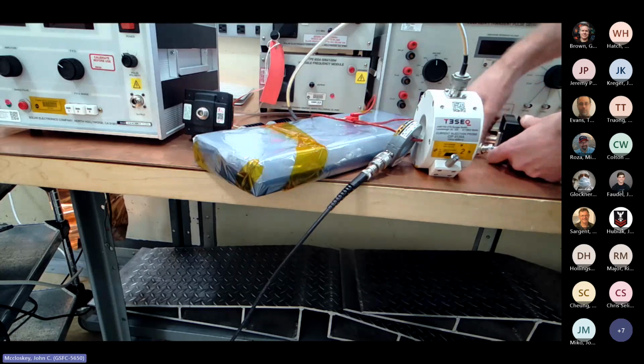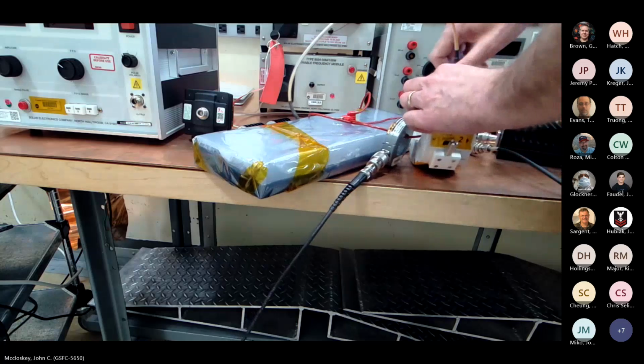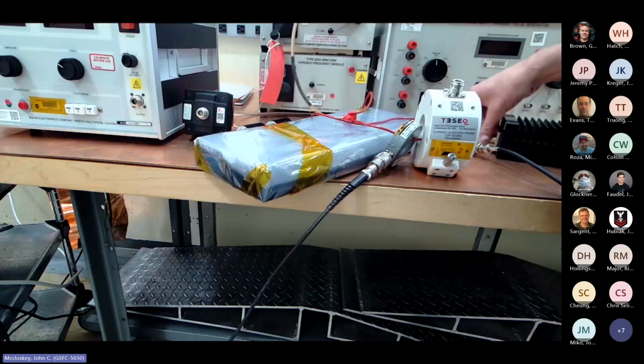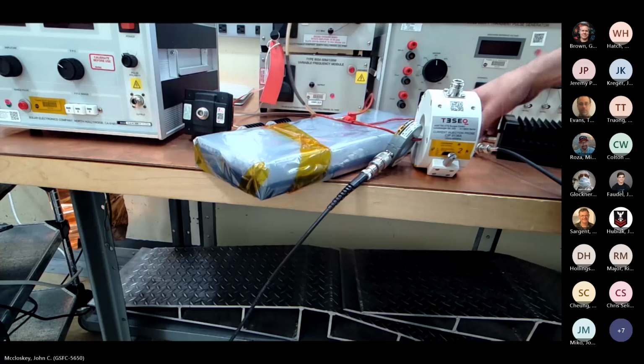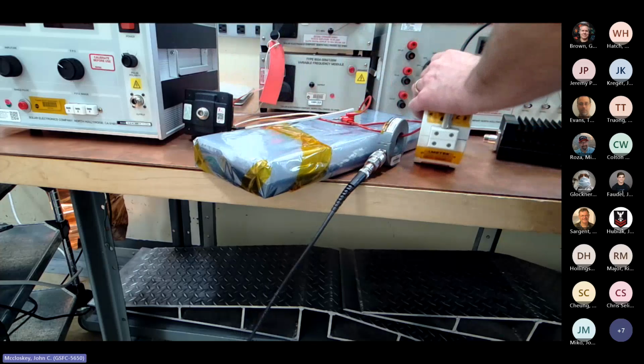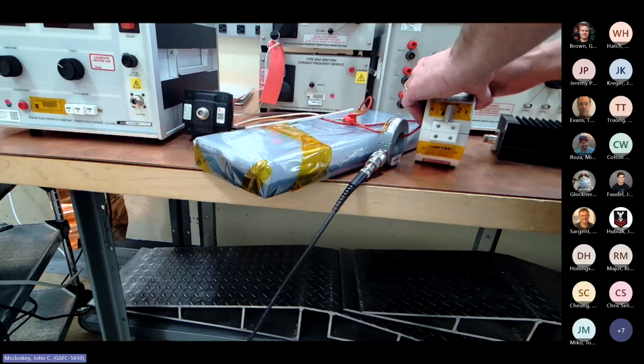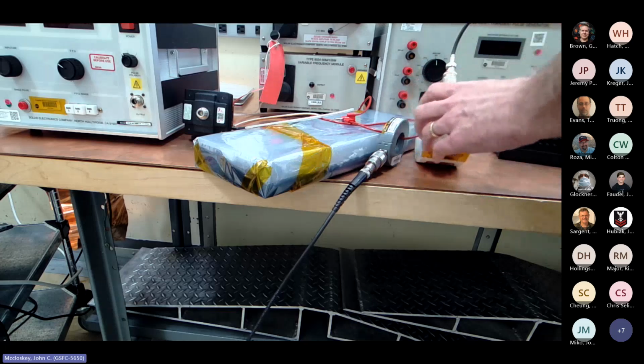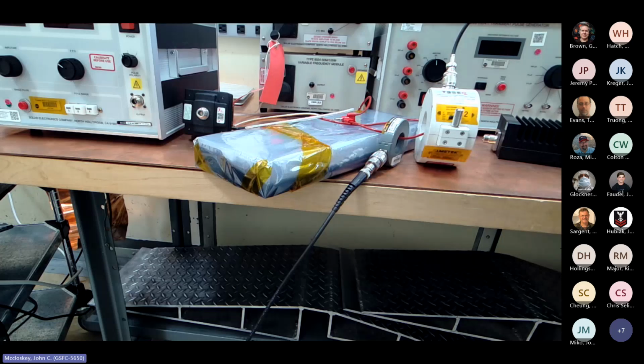So again, it's not cookie cutter. It's not always put 20 dB in line with your setup. It's a tool in your kit, depending on the drive signal you're trying to get and the capability of your equipment. If you have one of those other systems I was talking about, I can't remember the manufacturer, but they may have broader dynamic range. You might be able to get some of those lower signal levels in a more stable way. So part of the whole point of the pre-calibration step is to look at the signal you're getting and make any adjustments you can. Your options are kind of limited, but you can put some attenuation in, get a beefier drive signal, and so forth. It's all about thought process more than providing an answer.